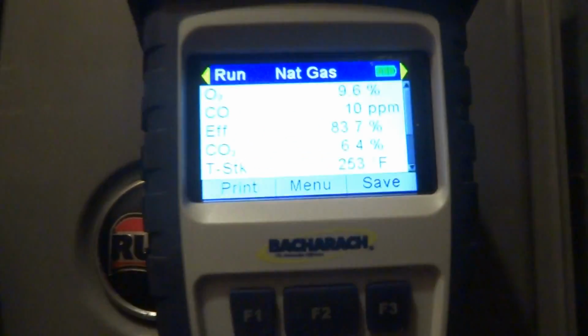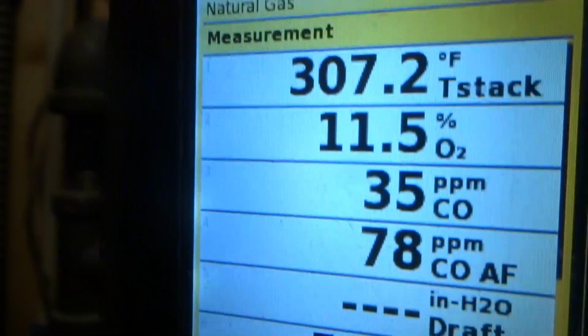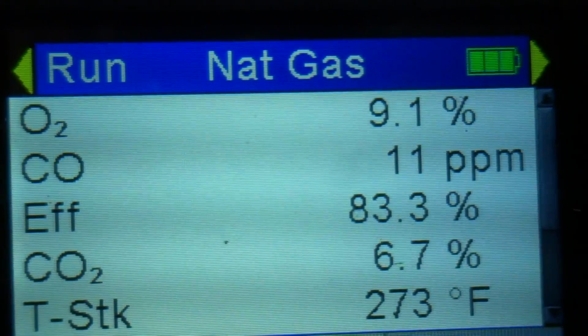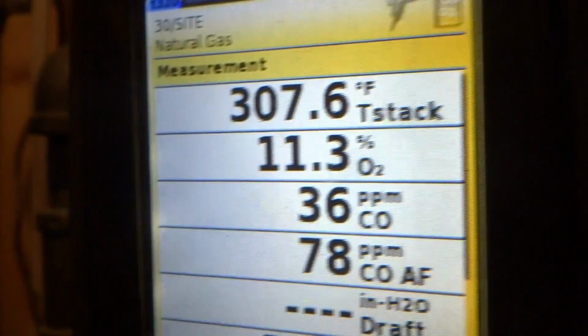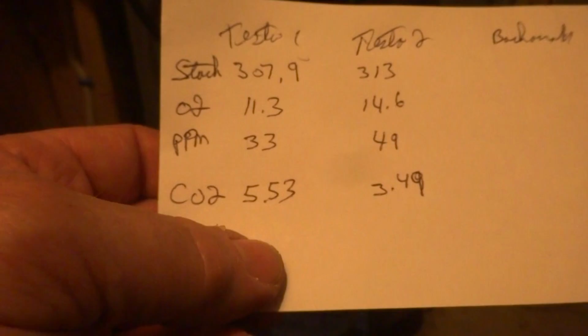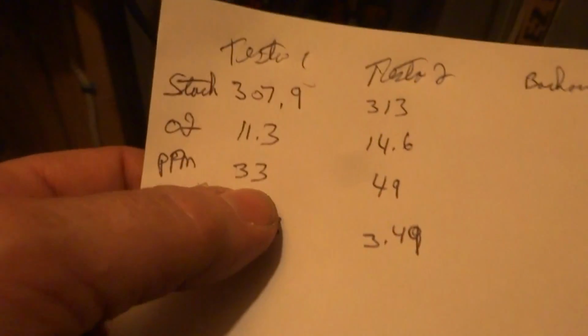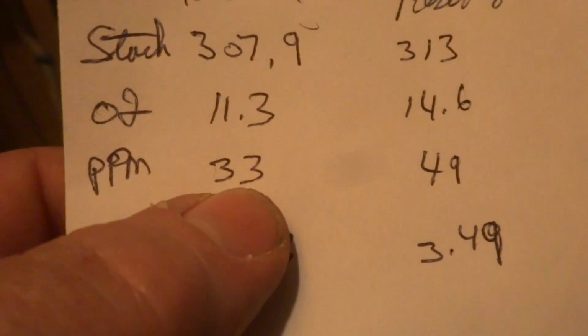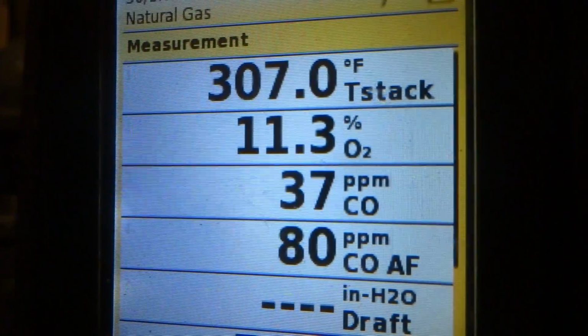I gotta get all the information down and call this guy from Bacharach. So we'll let it run for a bit and get the stack temperature up to the same. What's the stack temperature? 307. This one's 257. We'll let it run for a bit. See how low the CO is? Only 11, and this one is 36. This one's 33 - it's up to 36 now, but I've been running it a little bit longer.